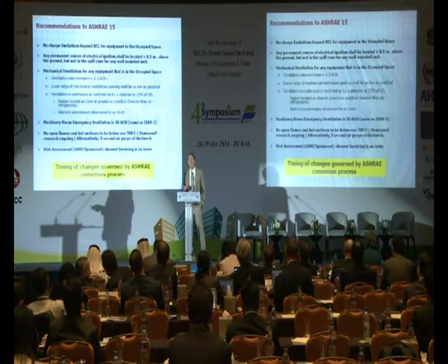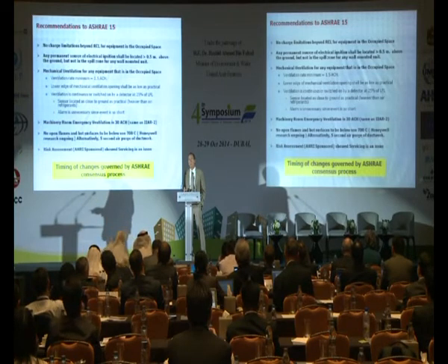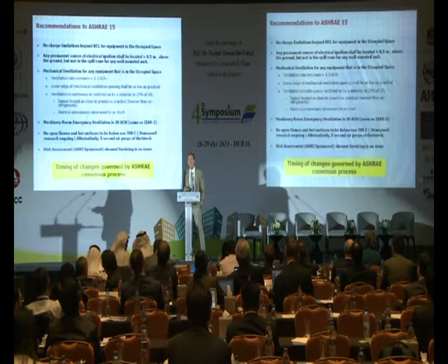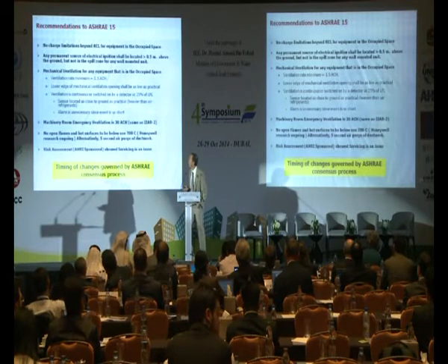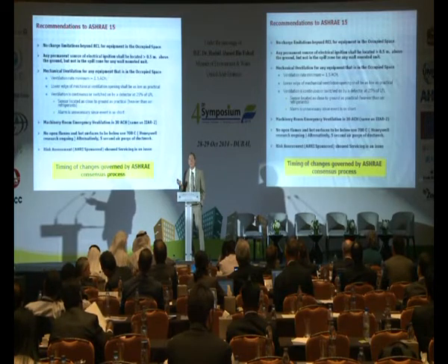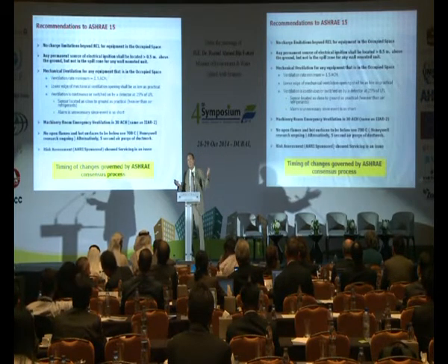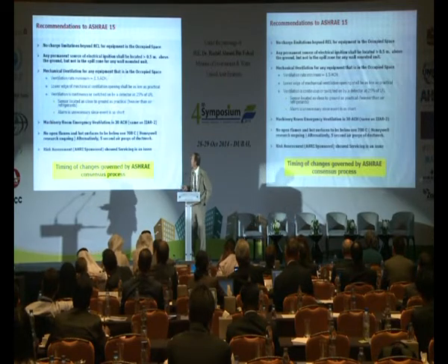They continue to do a lot of work to try and understand the consequences of adding oil and that type of thing to the refrigerant. But it seems that the whole class of refrigerants isn't capable of being ignited except by some pretty hot sources in terms of duct heaters and that type of thing. The second way you can do that is provide a little ventilation air. If refrigerant is accumulated in a ductwork, just purge it. It's safe in a matter of seconds.